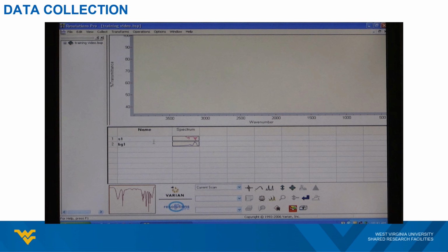Here, I would like to emphasize that the background spectrum in FTIR may change over time, which is often referred to as thermal drift. To account for this variation and ensure accurate results, it is common practice to frequently recollect the background spectrum after every significant break, before each new sample, or if you noticed unexpected features in the spectra.